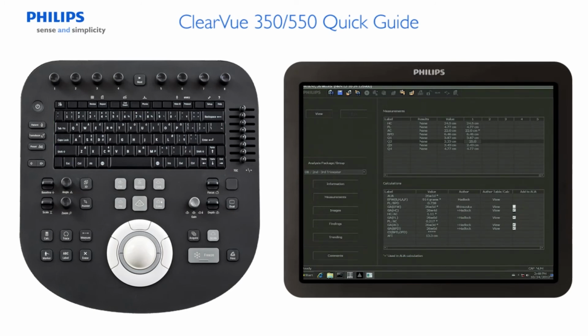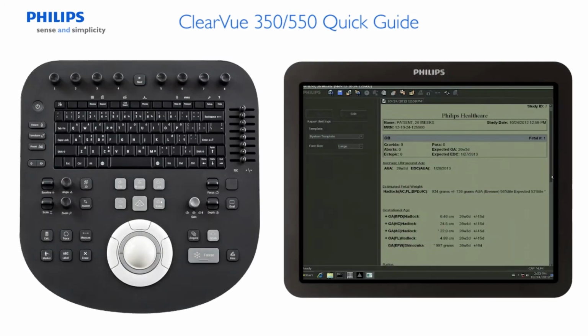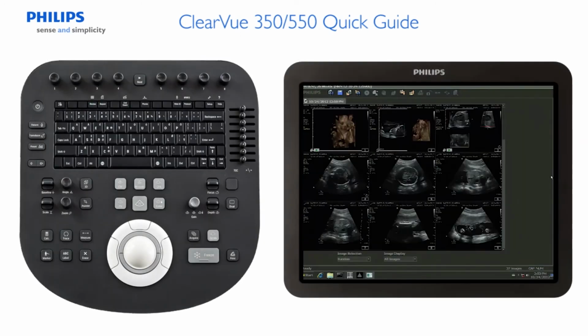To delete the measurement, position the cursor over the measurement you want to delete and press the left trackball button to highlight the measurement. Next, press the right trackball button. Select Delete and click Yes to confirm the action. To add images to the report, press Review, select the images, then click the Add Image to Report icon.